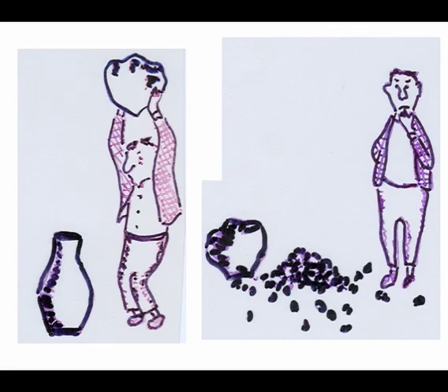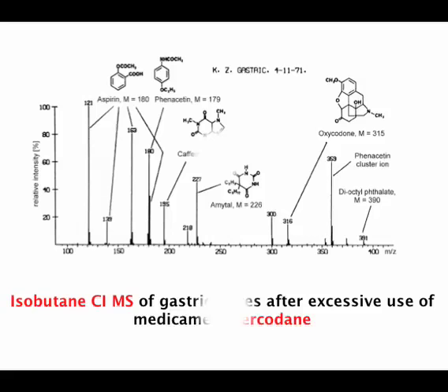The method in which we ionize the molecule with great power, it falls apart into thousands of fragments, and it's difficult to get to the structure. Until 10 years ago approximately, it was not possible practically to do the soft ionization. We had to do it the hard way, because there were no technical solutions for this. And most spectra that exist were done with the so-called high power hit of the electrons, and we were happy to get to the molecular weight. But today, we do so-called soft ionizations, and it's easier. You get more structural information.